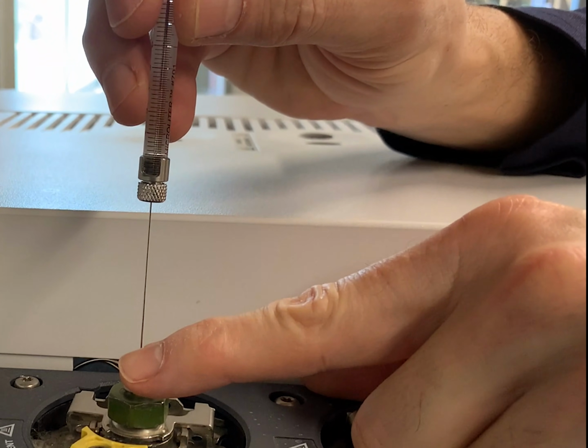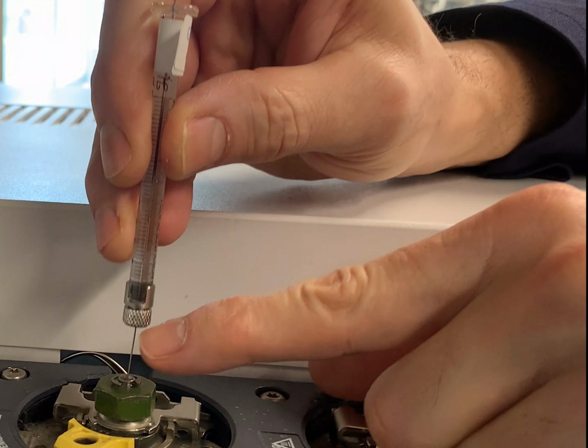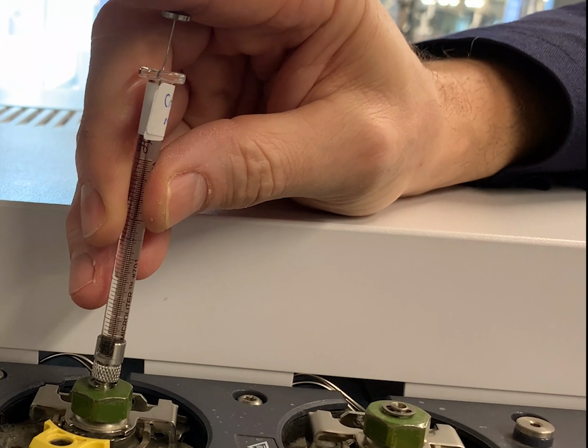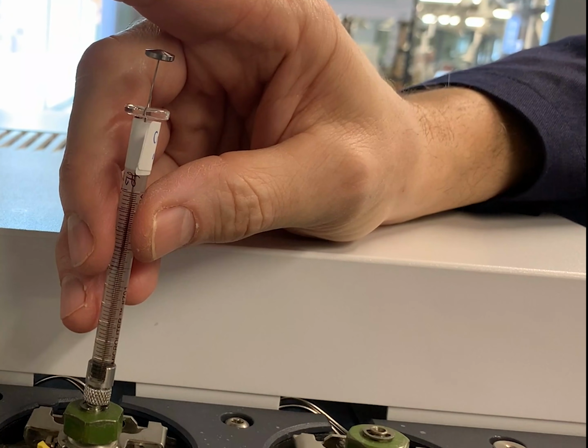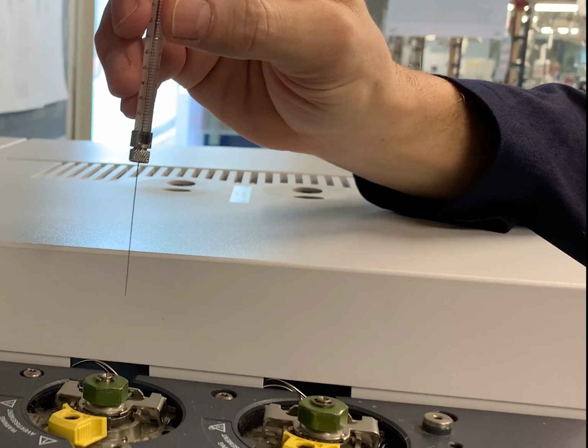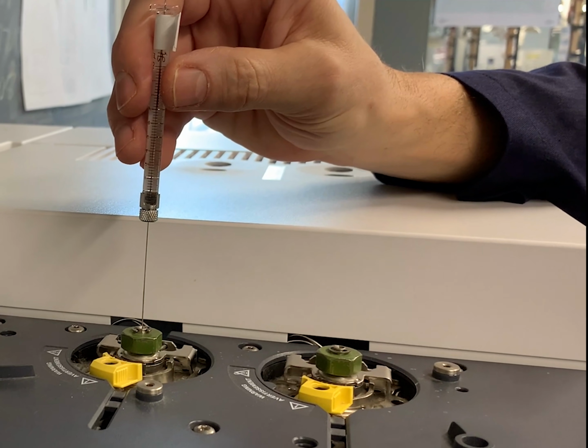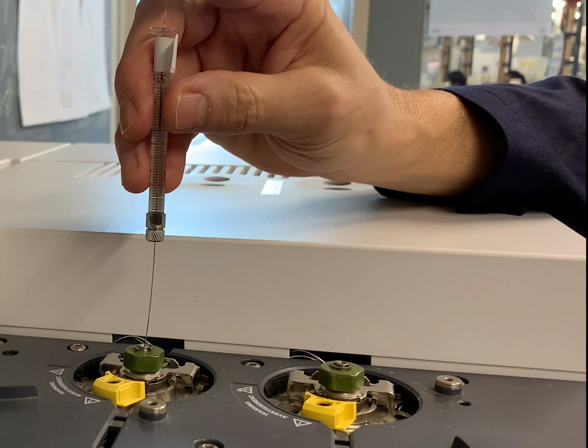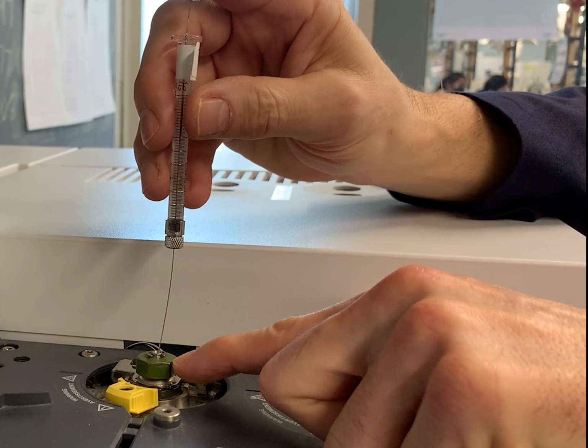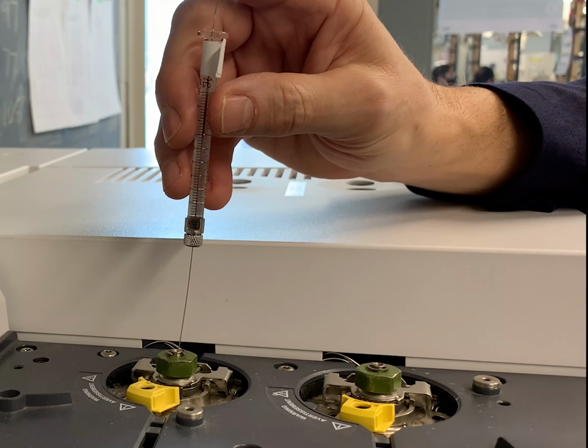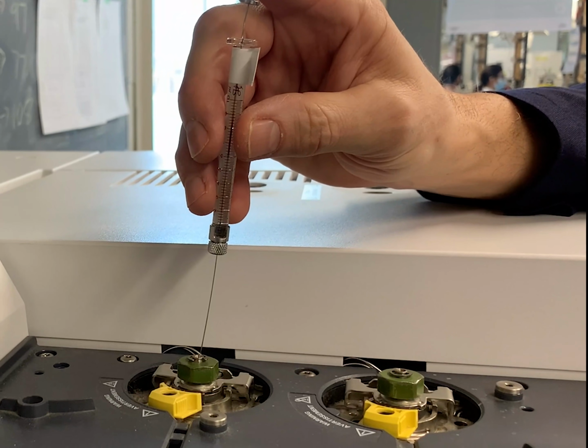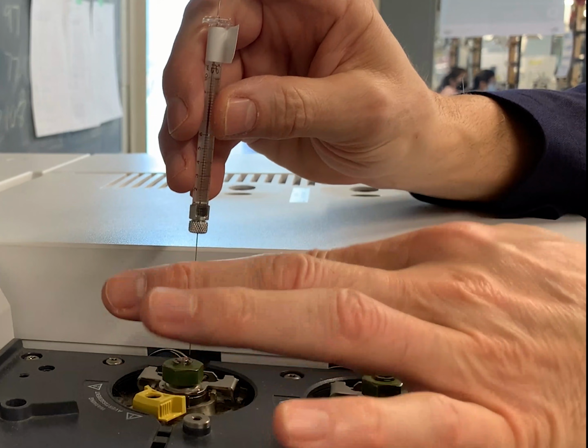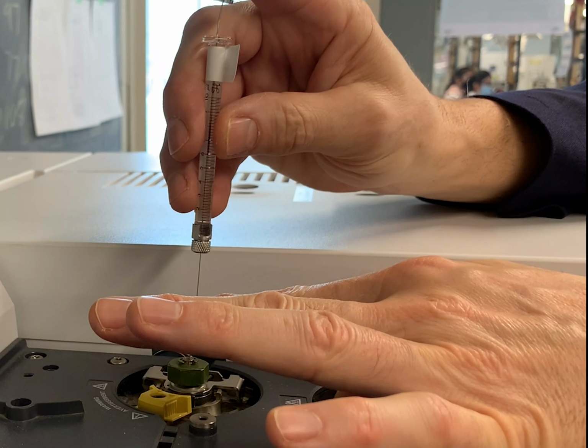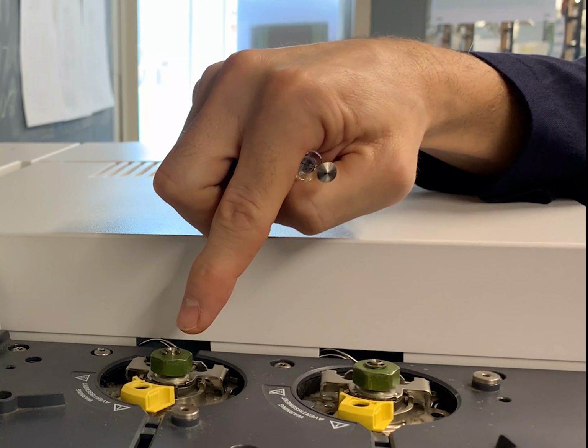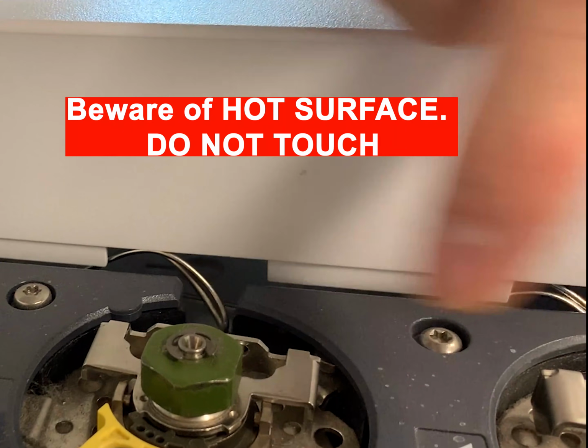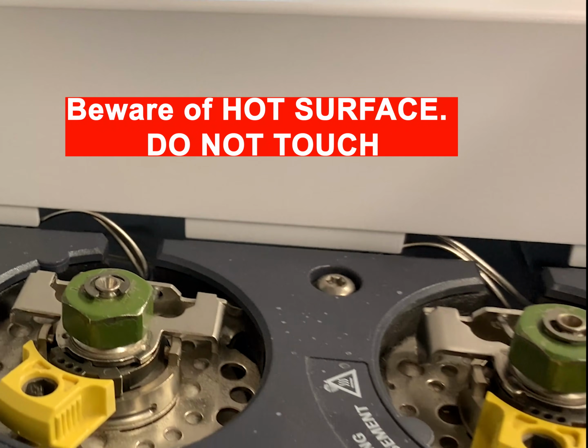You can use 2 fingers to guide it. Straight down all the way, do your injection, hit start. One of the other issues that people tend to do is they'll put their syringe and just leave it here and then do the injection. So we're injecting into this nut rather than injecting into the GC. Oh, by the way, when you are guiding this towards the injector port, these nuts are red hot. Do not touch the green nuts. They will burn your fingers.